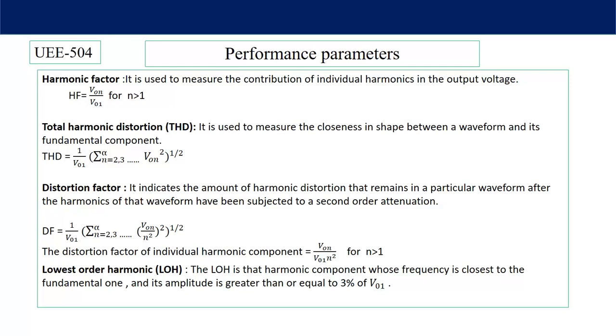The distortion factor of individual harmonics can also be found as V_0N divided by (V_01 times N squared), for N greater than 1. Then, lowest order harmonic (LOH) is the harmonic component whose frequency is closest to the fundamental and whose amplitude is greater than or equal to 3% of the fundamental. If the harmonic magnitude is less than 3%, we can assume our output waveform is close to the fundamental. All these factors are very important to decide the quality of the output waveform.